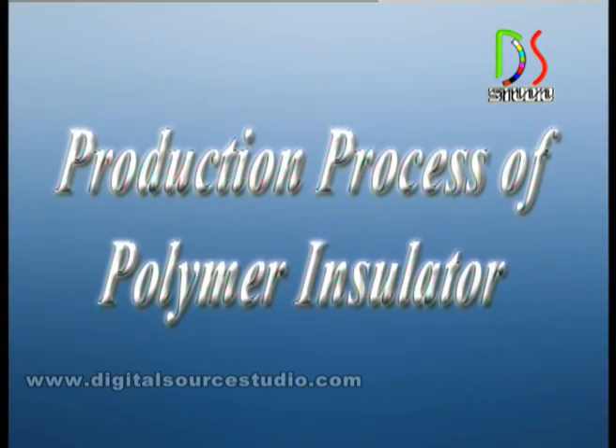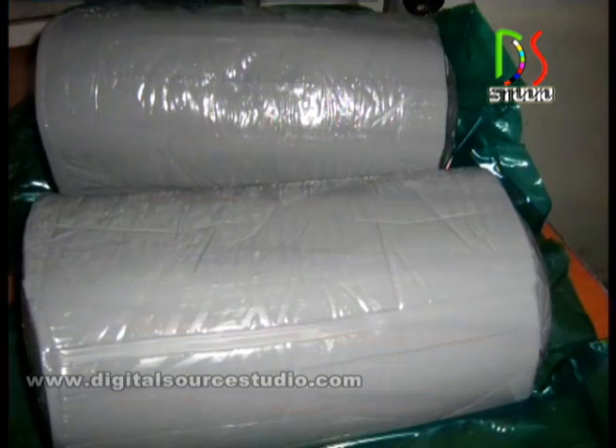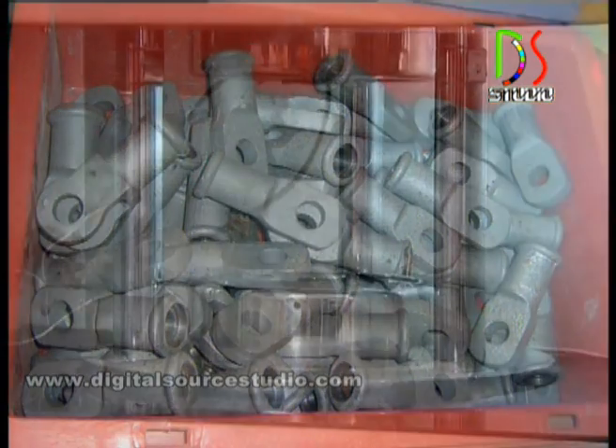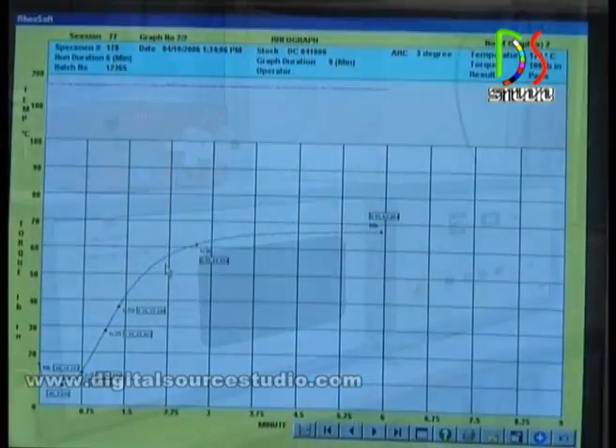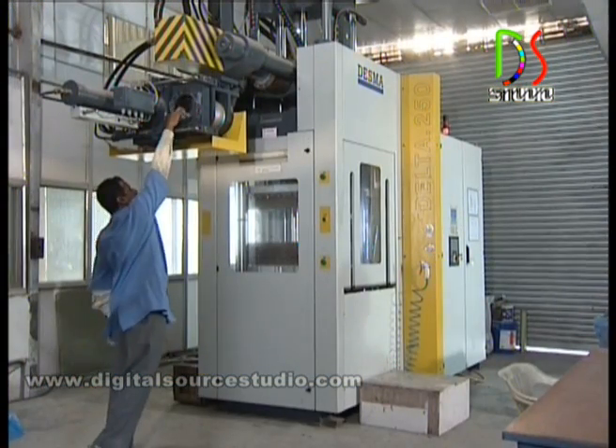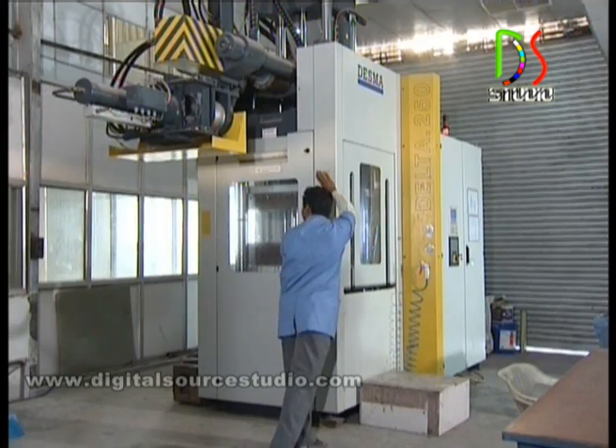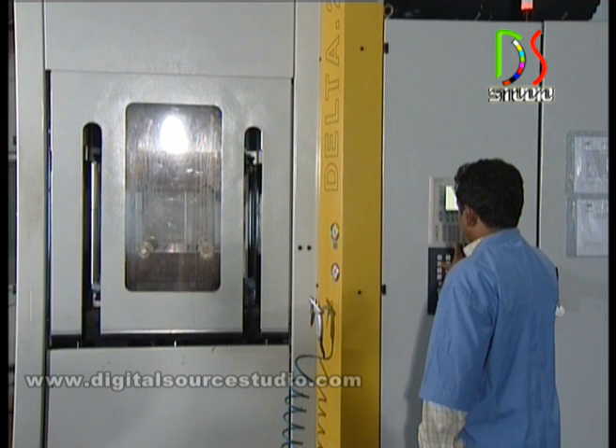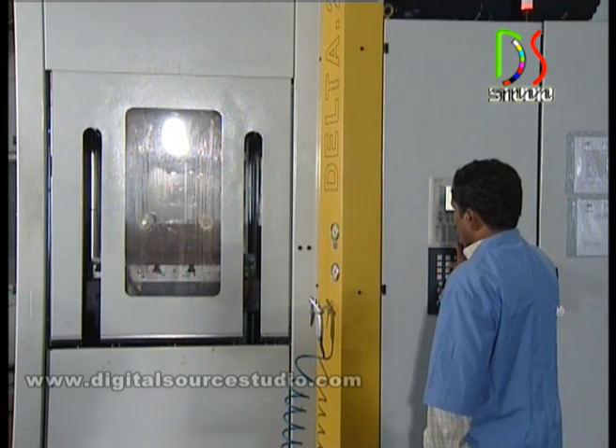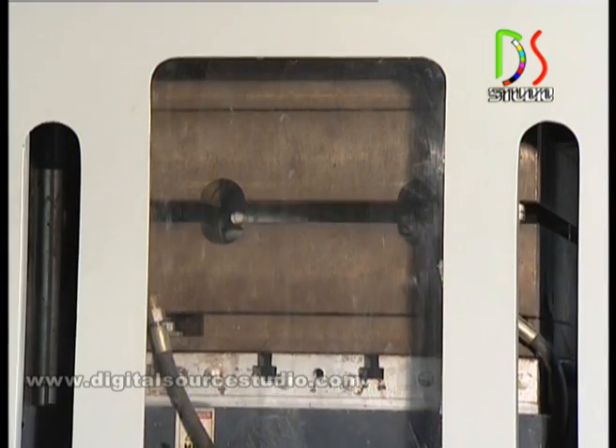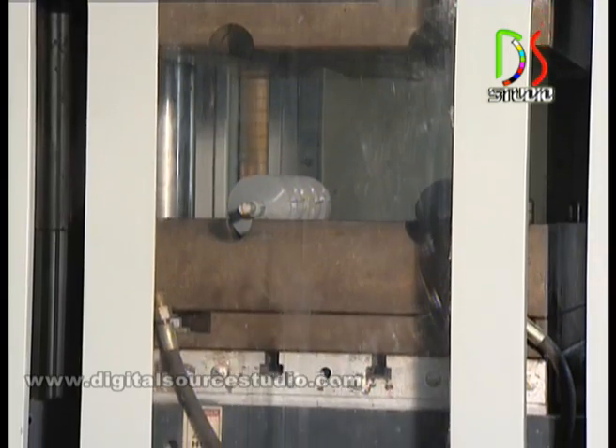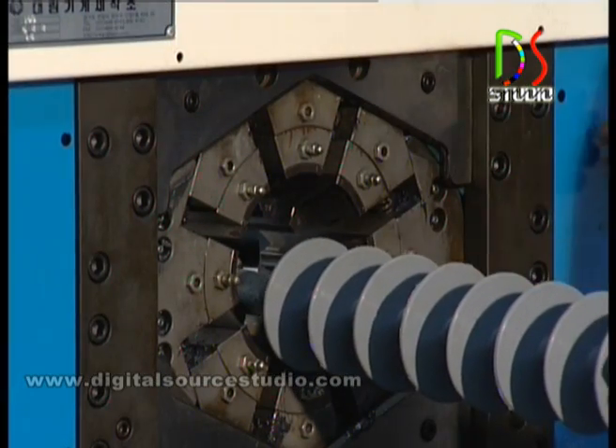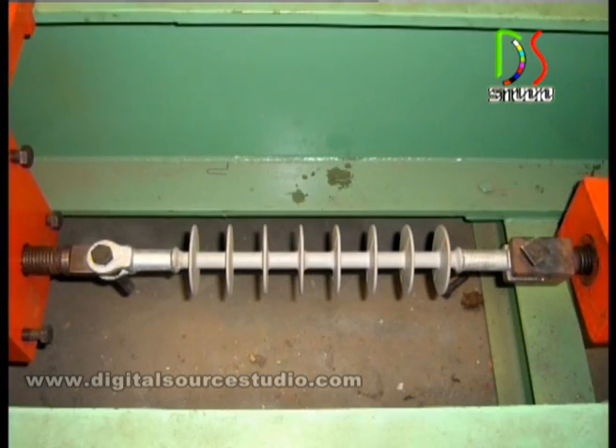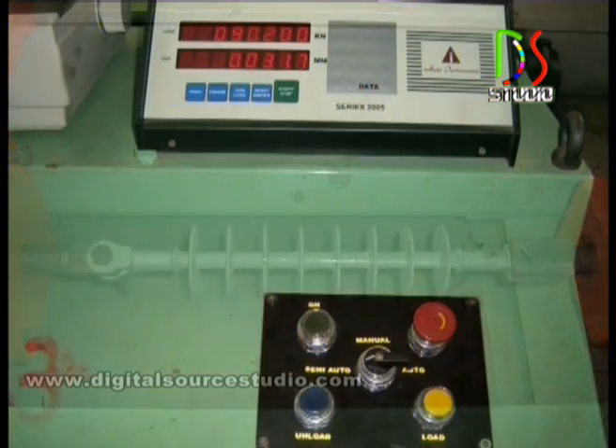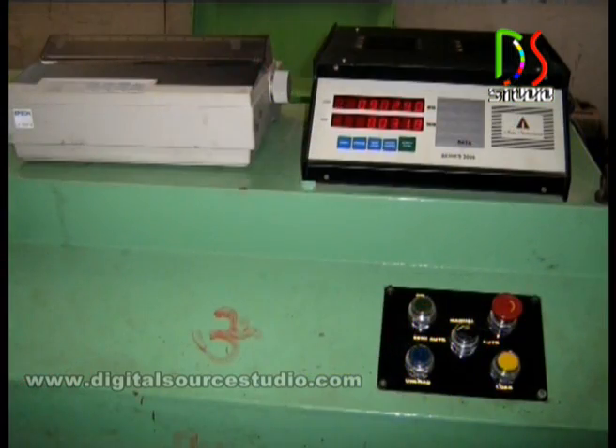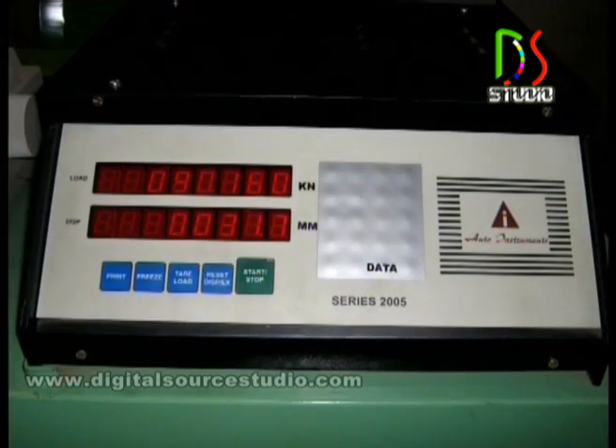Production process of polymer insulator. The raw materials, FRP rods, silicone rubber, and metal end fittings, are subjected to tests as per specific standards. Placement of specific primer-treated FRP rod is done. Automatic mold closes and clamping is done. Then silicone rubber is injected into the mold through the injection unit. This is followed by automatic curing of silicone rubber in the mold. The polymer insulator is ready with the end fittings crimped into the mold. 100% polymer insulators are subjected to routine tests as per IEC 61109. Mechanical load test.